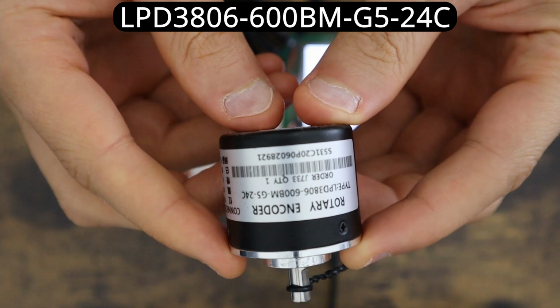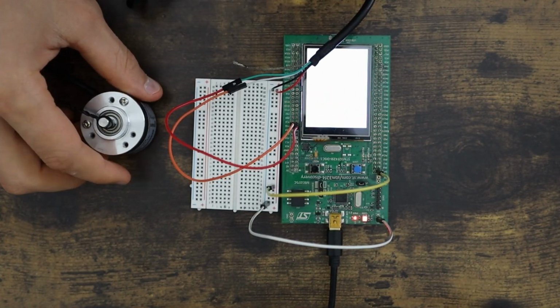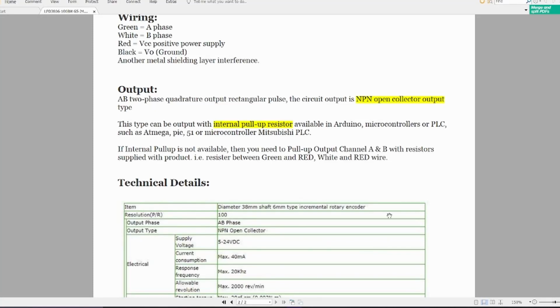You can see here the number of my encoder. So if I go to the datasheet and read about the output, here you can see this output is of type NPN, open collector output. Which means you have to pull up the output to get the right value. And here you see the hint.